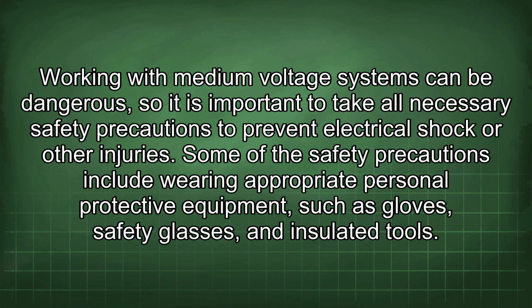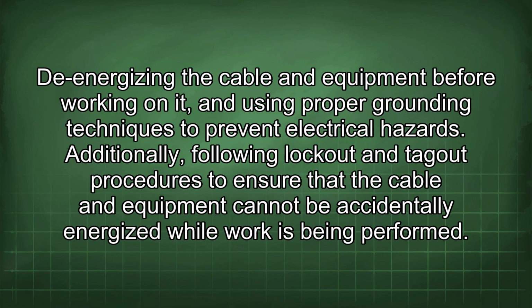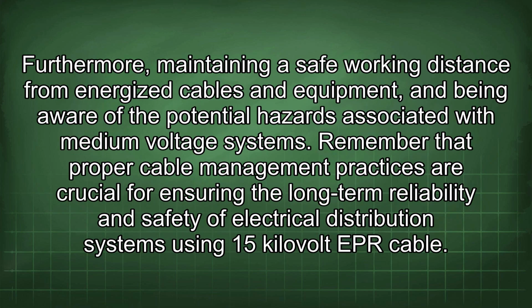Some of the safety precautions include wearing appropriate personal protective equipment such as gloves, safety glasses, and insulated tools. De-energizing the cable and equipment before working on it, and using proper grounding techniques to prevent electrical hazards. Additionally, following lockout and tagout procedures to ensure that the cable and equipment cannot be accidentally energized while work is being performed. Furthermore, maintaining a safe working distance from energized cables and equipment, and being aware of the potential hazards associated with medium voltage systems.